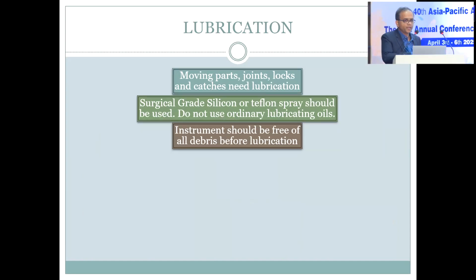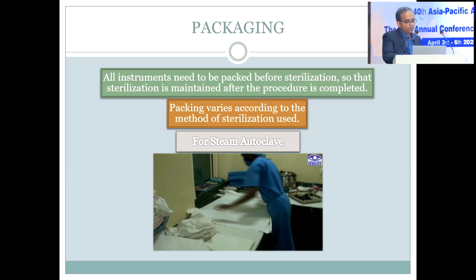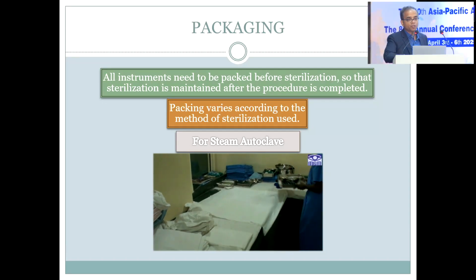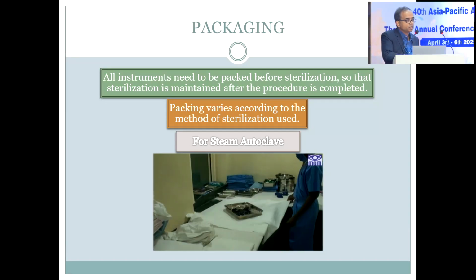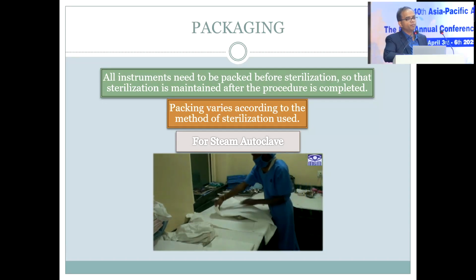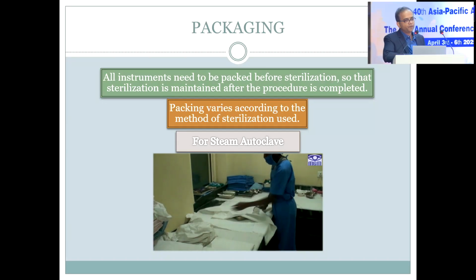For moving parts, we can use lubrication before it goes for sterilization, only when you feel that there is significant limitation of movement of your instrument. So surgical grade silicone or Teflon spray should be used, but not normal lubricating oils, because those oils will remain on the surface. Again, packaging for sterilization is very important, because if we don't do proper packaging, there can be immediate reinfection in our sets.